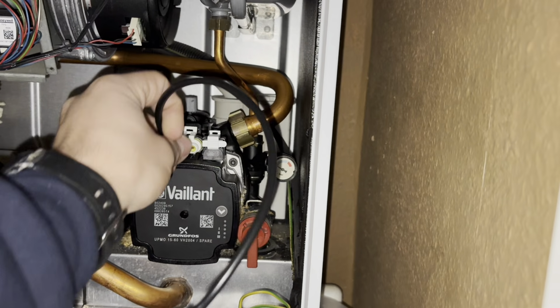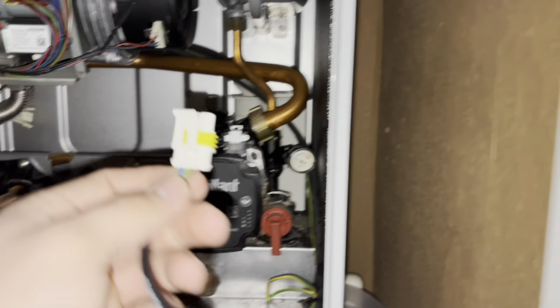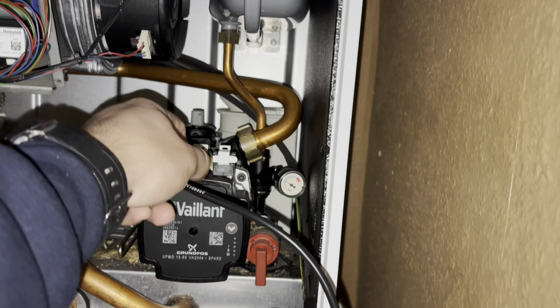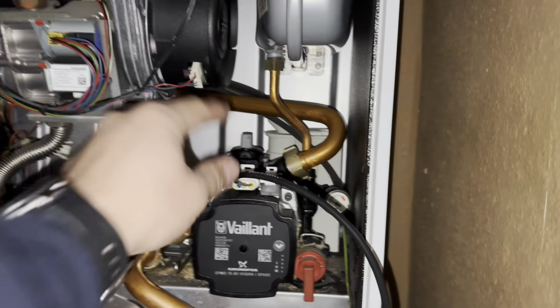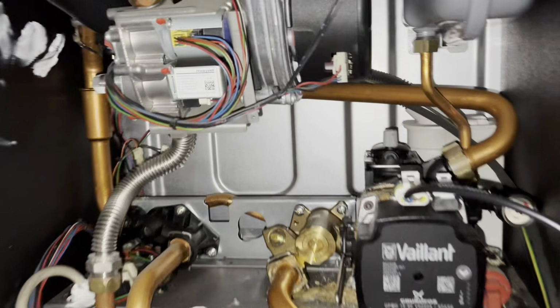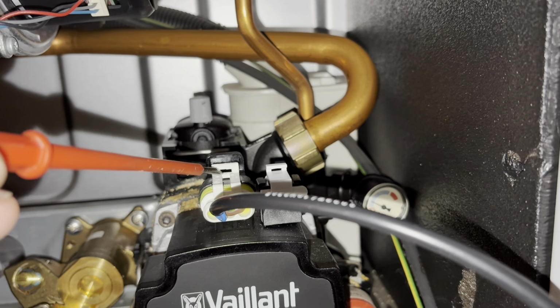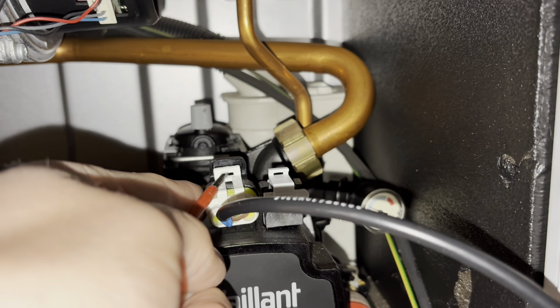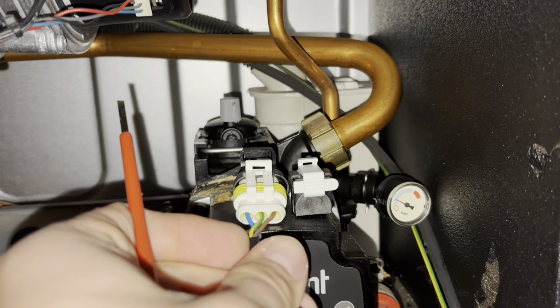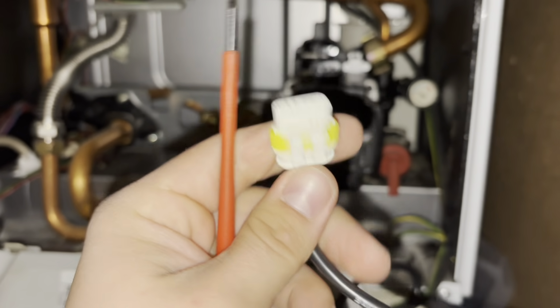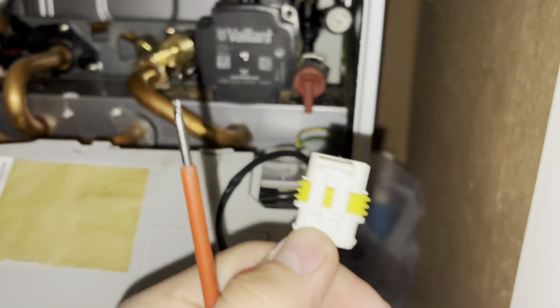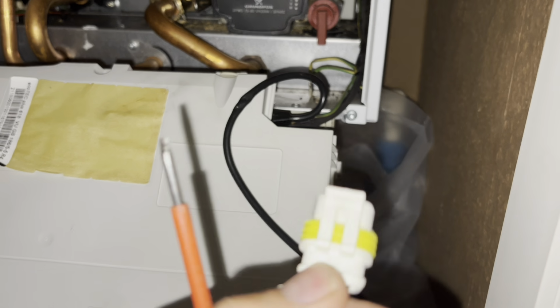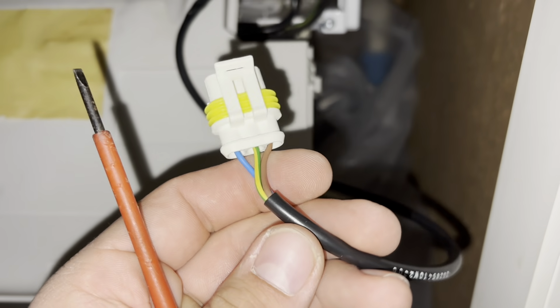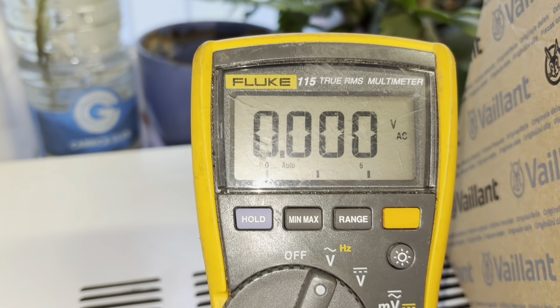but to make sure it is the pump, you can usually unplug this cable. What you would have to do is wedge a little screwdriver in here, lift that up, and then pull it out. I try to avoid pulling on the cables too hard, as you can rip them out. Very rarely, but I've seen it done. So as the boiler's now trying to fire up, you've got the brown and the blue cable. What you want to do is AC.